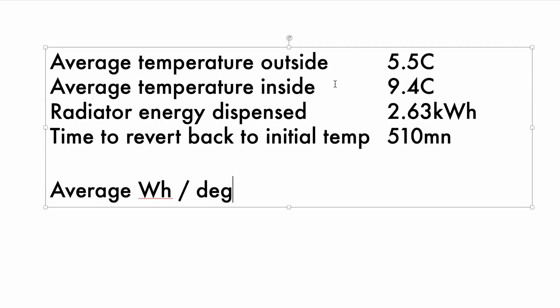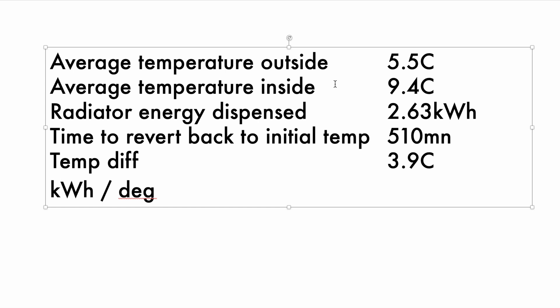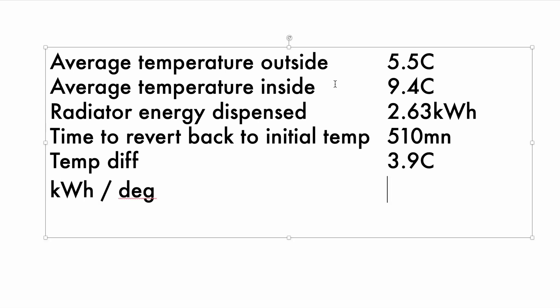The temperature difference is 9.4 minus 5.5 degrees. So, how many kilowatt hours for each degree of difference with the external temperature on average? That's 2.63 divided by 3.9, which equals 0.674 kilowatt hours per degree.